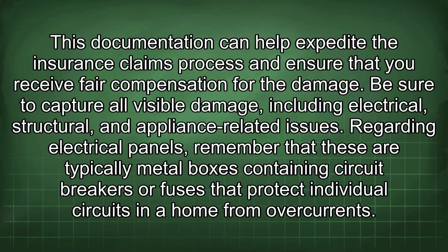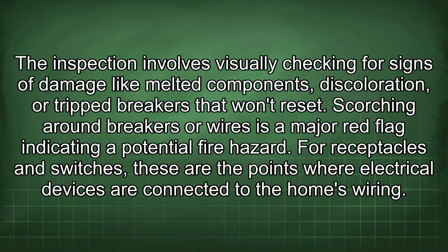Regarding electrical panels, remember that these are typically metal boxes containing circuit breakers or fuses that protect individual circuits in a home from overcurrents. The inspection involves visually checking for signs of damage like melted components, discoloration, or tripped breakers that won't reset. Scorching around breakers or wires is a major red flag indicating a potential fire hazard.